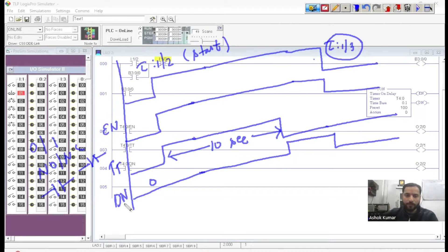Right? Now come back. So I'll start. As I start, we can see enable and TT are high. The timer is providing the delay. The accumulator is showing you each and every value. After 10 seconds, as per the graph, TT should go low and done should go high. Look at this. After 10 seconds, TT is low and done is high. And if we stop manually, all goes low.